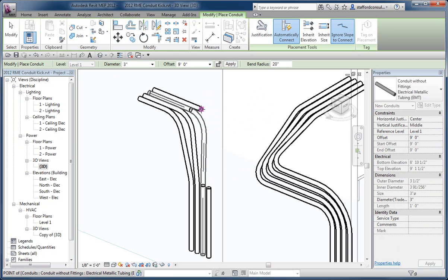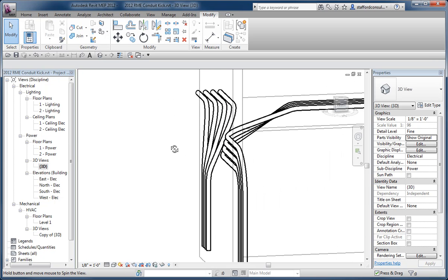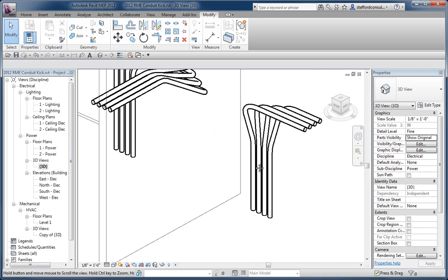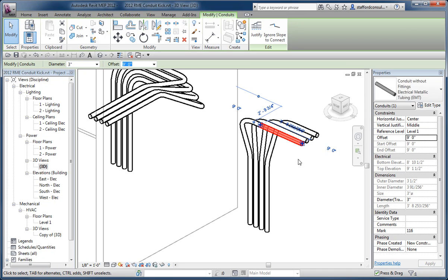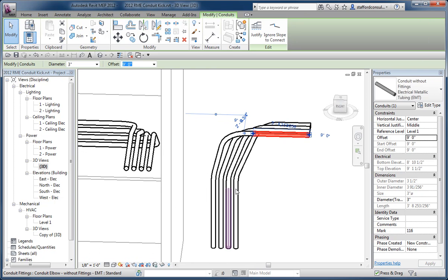if the elevations are too close, then what happens is that Revit has a harder time generating the correct sort of conduit run between them. You can see it's much more gentle in its approach at this point. So 6 foot compared with the 9 foot elevation of this conduit here resulted in clumsy connections.